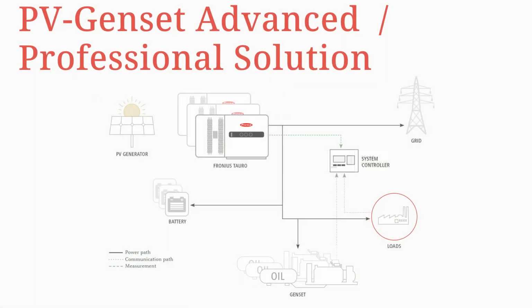Good. So going forward, the PV-Genset Advanced and Professional solutions are basically the same thing, they just differ a bit in application. Given the single line diagram, as you can see in this case, the solution entails the integration of the system controller. It could be on an already existing system, in which case we call it the PV-Genset Advanced solution. That entails the retrofitting of a system controller into an already existing genset system. The professional solution entails a situation where, apart from the system controller, you have multiple gensets that also have their respective controllers.